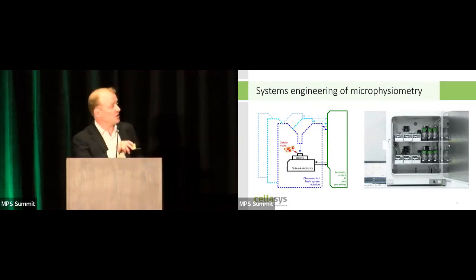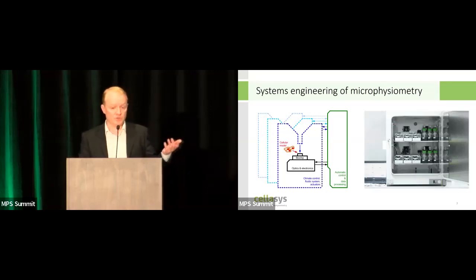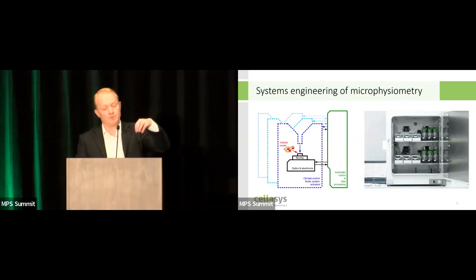That is how our approach looks. Here we have 6 chambers with 6 biochips where we can put the cellular models. On the back side, we have a pump. And here we have different fluidic modules where, before the start of the experiment, we can place the cell culture media in different flasks: the flask with cell culture media and the drug under investigation, and for example media for the control, everything mounted in the incubator. And here we have the control unit right beside it.